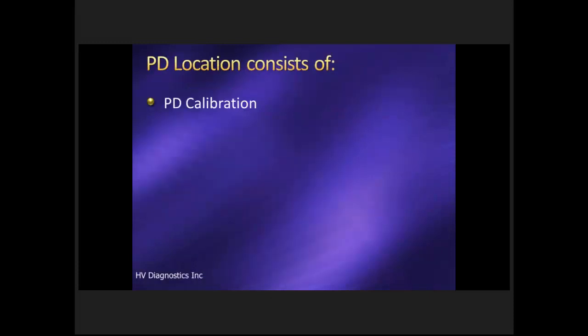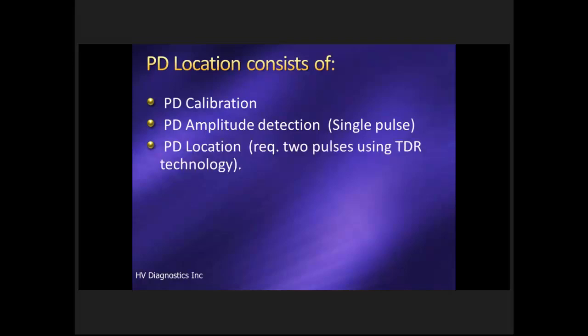So PD location consists of the calibration that we do, and we have a small calibrator that you can use offline. Clearly online, when you're relying purely on operating voltage, there's no way to physically hook onto the cable, so calibration can become very difficult, if not impossible. But we always calibrate each and every time we go out there with PD, to make sure that we understand how big the signal is. We do PD amplitude detection, that's obviously how big the PD is, called the Coulomb value. And then clearly, based on the two pulses, we can do location of the PD site as well.